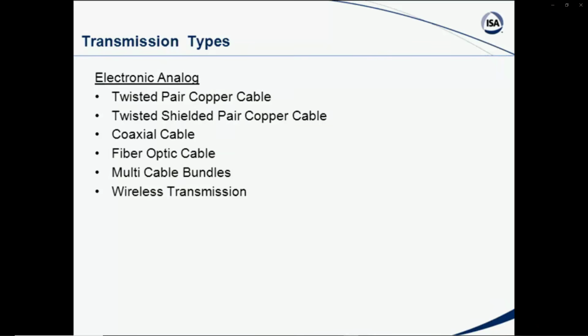Well, in the case of electronic analog, of course, I think all of you are familiar with twisted pair copper cable or twisted pair shielded copper cable. Coaxial is used in many cases for certain benefits that it has, and fiber optics has some advantages and is used in many cases, savings on room and space, etc. But you'll also see multi-cable bundles, and one of the more recent, wireless transmission, is becoming more and more ingrained in some of our industrial process units, because there they can take advantage of the circumstances of communicating that around the unit. The security has become much better now, and so wireless transmission, not only for just data acquisition, but even being used for control.